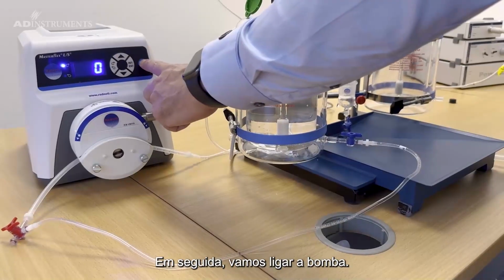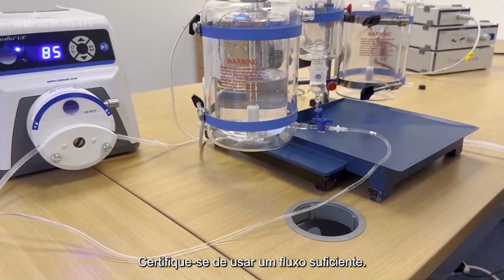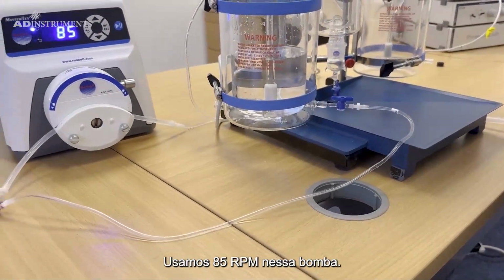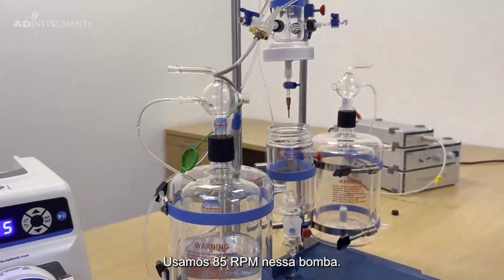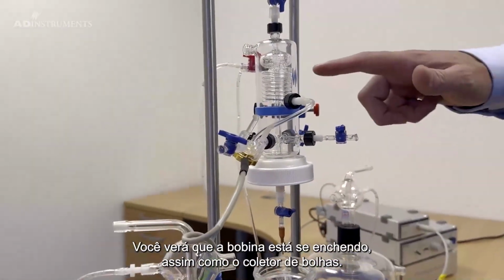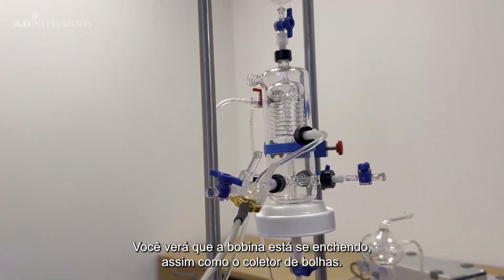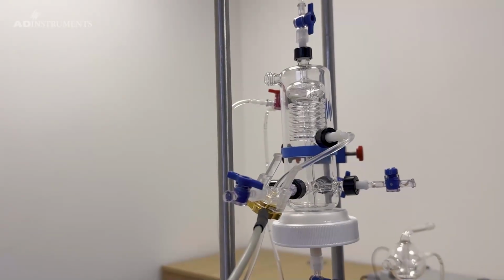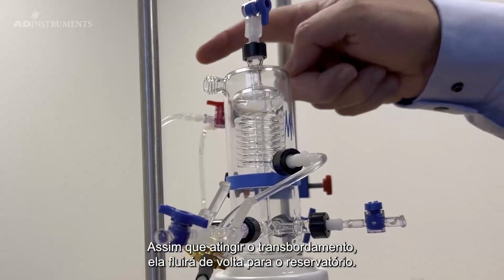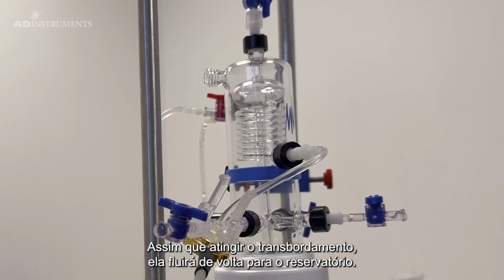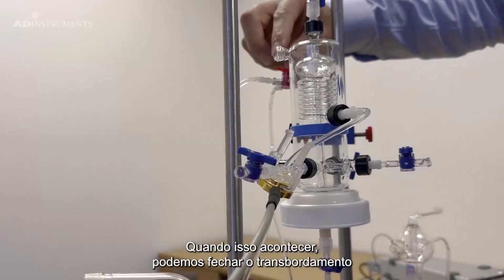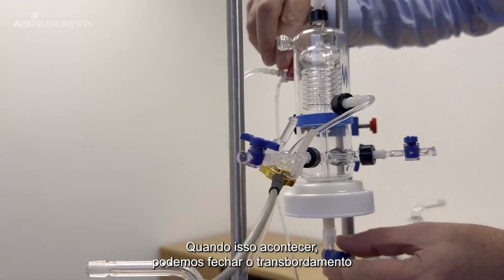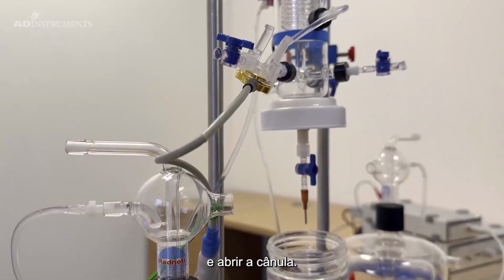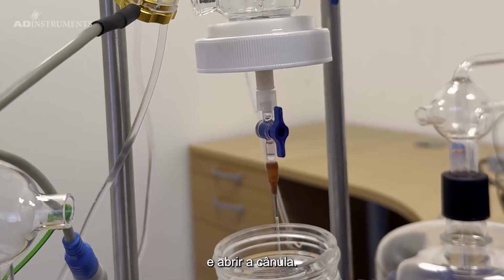So next we start the pump. Make sure you use enough or sufficient flow. We use 85 RPM on this pump. You'll see the coil is filling up and so is the bubble trap. As soon as it hits the overflow, it will flow back to the reservoir. Once this happens, we can close off the overflow and open up the cannula.